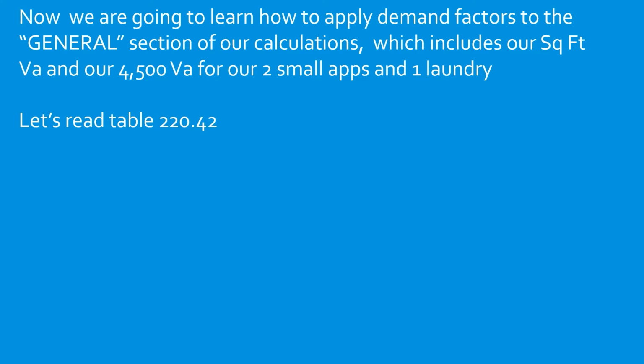Okay, the second black bold heading to the right says portion of the lighting load to which the demand factor applies. Okay, so it's broken down in portions, and don't be overwhelmed by it. We're going to break it down step by step, and hopefully I've created the easiest way to work through this part of the load calculation. Then on the far right, it says the demand factor. That's our last black bold heading, and that's the demand factor that you apply. But you guys are starting to be pros by now, really understanding that this is just a multiplier, isn't it?